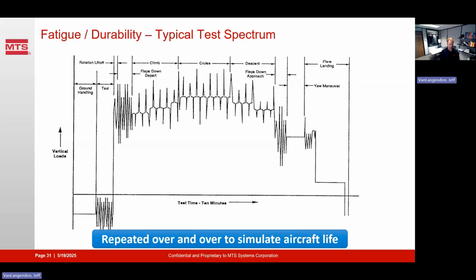For a fatigue test that's going to take months or years, you want to run as fast and accurately as possible. A big part of that is sizing all the hydraulic equipment appropriately, including the size of the actuators and the servo valves, which is critical, and then upstream of those, the hydraulic distribution and ultimately the hydraulic power system.